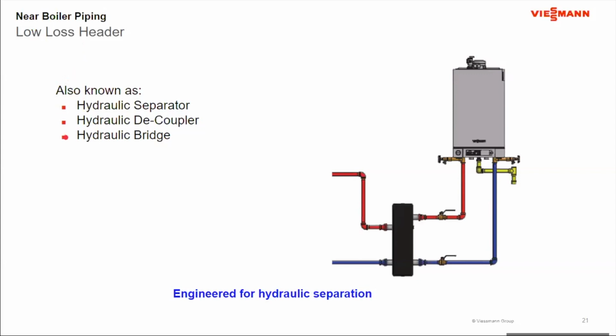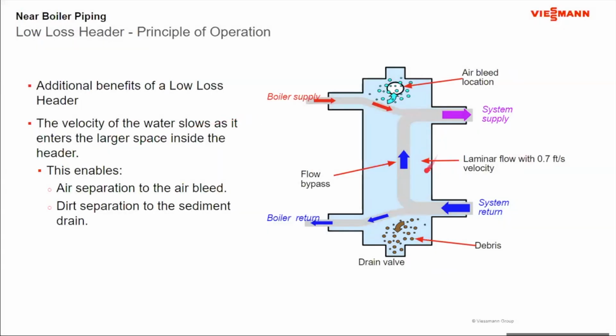Now, how they work is internally, the internal area within the hydraulic separator is much larger than the incoming piping connections. And in sizing, the body of the hydraulic separator is designed for a flow rate of about 0.7 feet per second velocity inside there. At 0.7 feet per second, inside the body, there's virtually no pressure drop whatsoever. So that's how we get this hydraulic separation, so that what happens on the system side does not affect what's happening on the boiler side. And then what will happen is through the body of the low loss header, you'll see water movement to balance any unequal flow on either side of this low loss header.